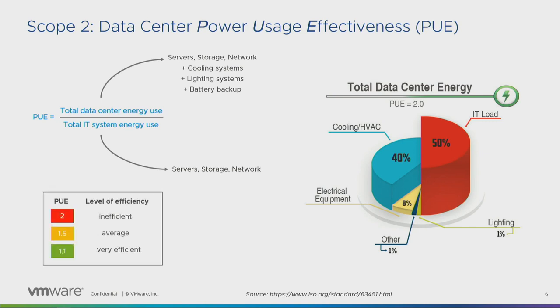A PUE of 2 is actually very bad. On average in France it's 1.5 to 1.7 PUE, and the industry tends to get as close to 1 as possible, but the most efficient data centers are around 1.1 to 1.3.